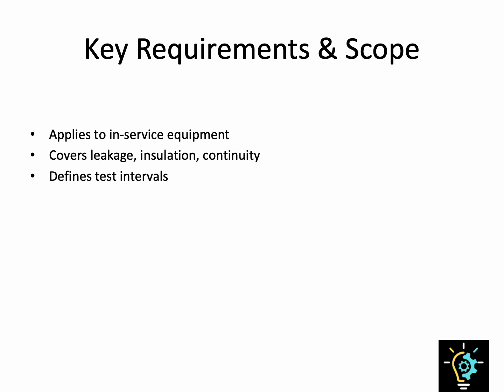What is the scope of IEC 62353? It applies to in-service medical devices, the devices that are already being used in hospitals and clinics, as well as equipment that's already been repaired and needs verification before going back into use. What do the tests cover? They cover the basics of electrical safety: insulation resistance, protective earth continuity, and different types of leakage current.